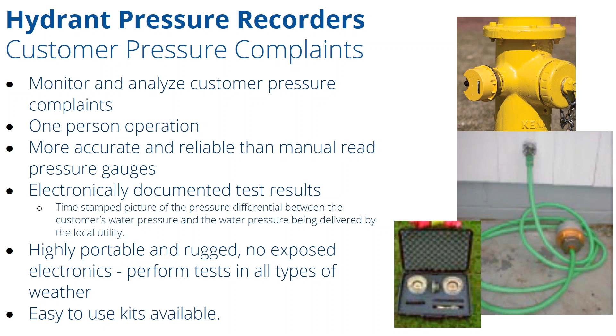So what you would do is hook our hydrant pressure recorder into the fire hydrant, energize it with water under pressure, and let it gather this very high accuracy data. And then at the end of the test, you're able to show, using a mobile computer out in the field, the homeowner what pressures were being recorded on the utility side of things, as well as on the customer side.